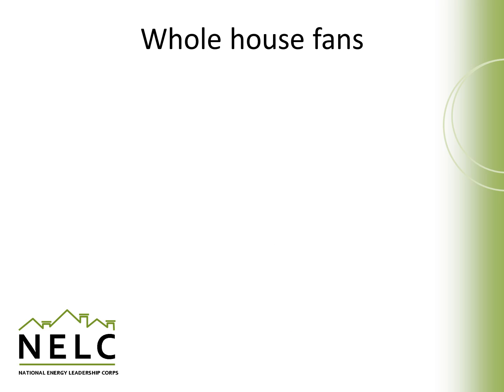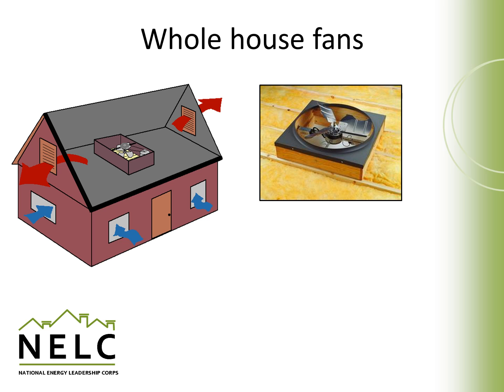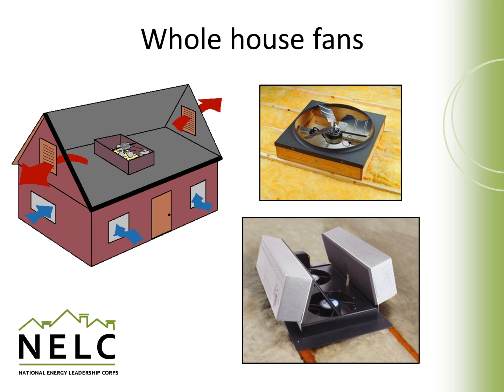Whole house fans are a great tool to introduce cool air in the summertime and exhaust hot air. They're a wonderful technique when you live in a place that gets cool in the evening. The fan typically sucks air out of the whole house and up into the attic where it's ventilated outside, creating a draft that draws air in through open windows. One caveat is that when they're not running, they can be a huge source of air loss up into the attic, so they should be well insulated, much like an attic hatch. Newer models come with doors and built-in insulation so they can be well sealed when not in use.